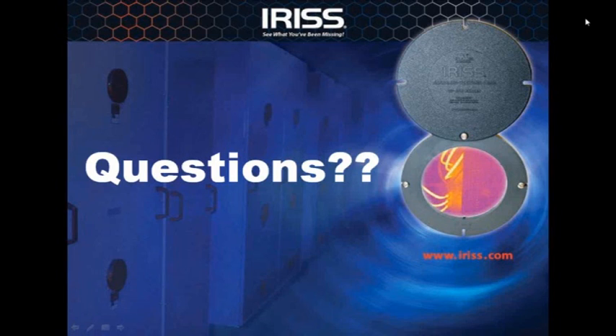I really do. So my viewpoint on this is, let's take a corporate view. If your corporate mandate states that any modifications that you do on your switch, you need to get UL back in, or a certification body back in to recertify the switch, then that's exactly what you should do. If it doesn't, then why should putting an ultrasound port or an infrared window change that mandate? So long as you're putting it in and it's correctly tested and certified by UL, IEEE, etc. But the official guide is to speak to UL. They're not ogres, and I'm sure they'll give you more advice, better advice than I can.